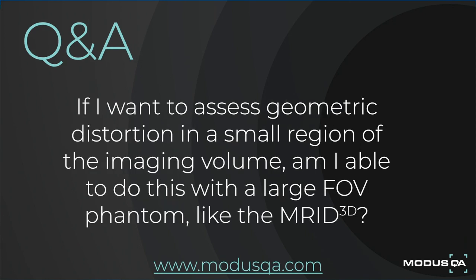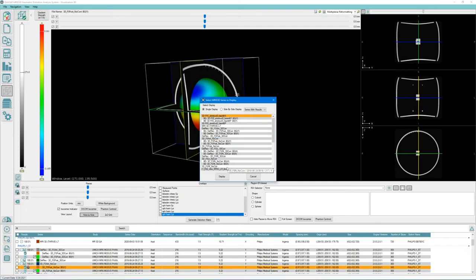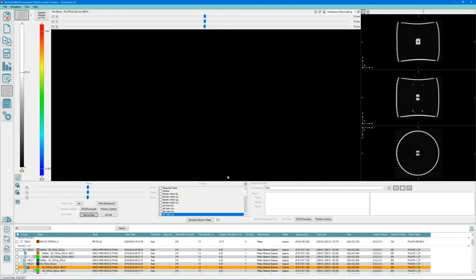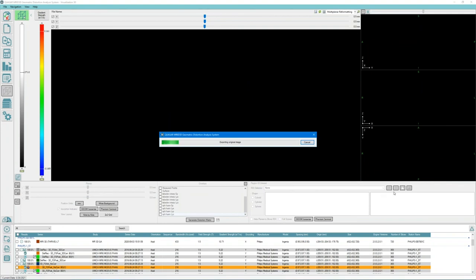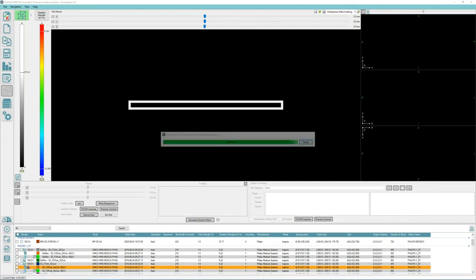If I want to assess geometric distortion in a small region of the imaging volume, am I able to do this with a large field-of-view phantom like the MRID 3D? Yes, absolutely you can do that. We have an ROI selector that one can invoke. This can be customized. We have some standard settings developed in collaboration with MR-Linac manufacturers for daily, weekly, and commissioning QA requirements.